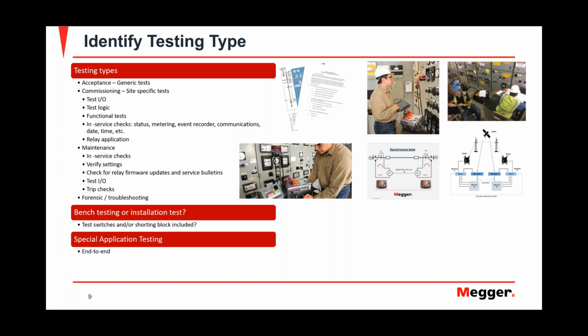Are you doing any special application testing, like end-to-end? Let's say you're doing line differential testing, where you require 2 test sets on either side, and you need communication in between. You may need a GPS depending on the transfer scheme in order to sync up the time for both test sets. So that requires more equipment. So let's say you don't have that equipment available and they tell you, hey, we need you to go tomorrow. You could stop. Hey, man, everything they're saying here is for a line differential test. I'm going to need more equipment than what I got in my truck right now.